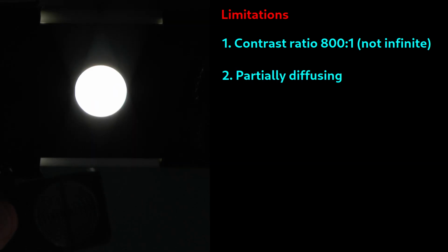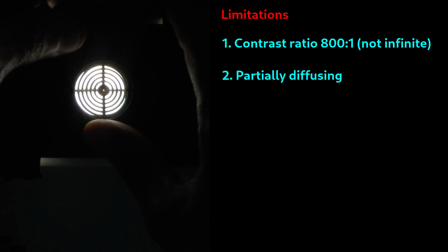Also, the PUMA SLM is not completely optically clear. It has some diffusing properties. For this reason, it cannot be used behind the objective lens, for example, to effect Fourier filtration in the back focal plane of the objective. And, when used in the lower focal plane of the condenser, it will blur the image of the field stop, so will not permit full Köhler illumination. This latter issue is not practically important in most cases, because the field stop image is not as important in reducing internal reflections in a PUMA scope as it is in some other and older microscopes.